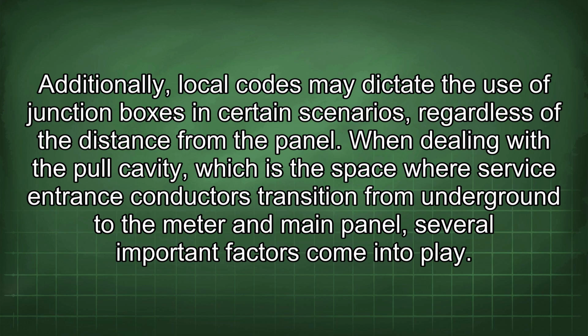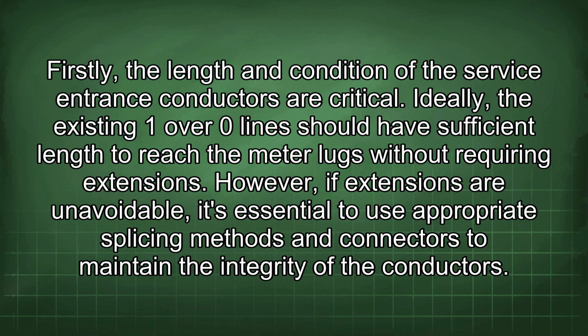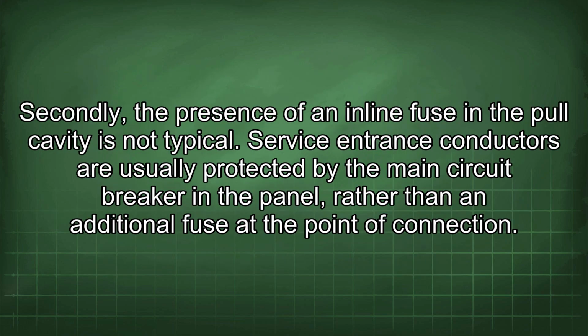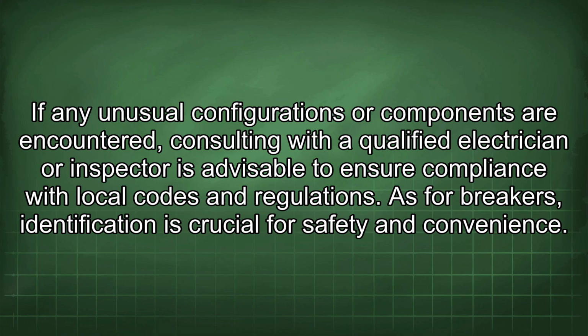When dealing with the pull cavity, which is the space where service entrance conductors transition from underground to the meter and main panel, several important factors come into play. Firstly, the length and condition of the service entrance conductors are critical. Ideally, the existing 1/0 line should have sufficient length to reach the meter lugs without requiring extensions. However, if extensions are unavoidable, it's essential to use appropriate splicing methods and connectors to maintain the integrity of the conductors. Secondly, the presence of an inline fuse in the pull cavity is not typical. Service entrance conductors are usually protected by the main circuit breaker in the panel, rather than an additional fuse at the point of connection. If any unusual configurations or components are encountered, consulting with a qualified electrician or inspector is advisable to ensure compliance with local codes and regulations.